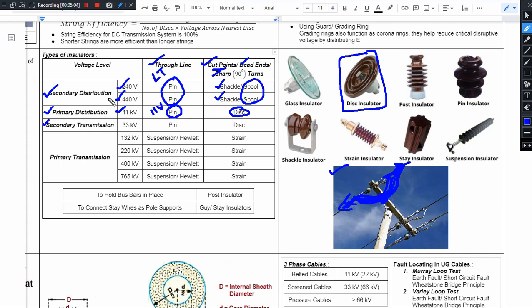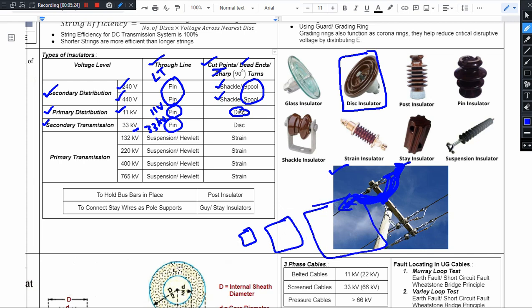For secondary transmission (33 kV), on the through-line we use 33 kV pin insulators. Pin insulators are limited to 33 kV due to mechanical strength constraints — the conductor is very large and heavy. For cut points, dead-ends, and sharp turnings at 33 kV, we use disc insulators. At 33 kV, we use a string of multiple discs, which technically becomes a strain insulator, but we still refer to it as a disc insulator here.